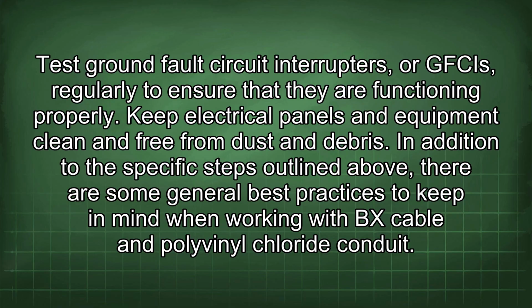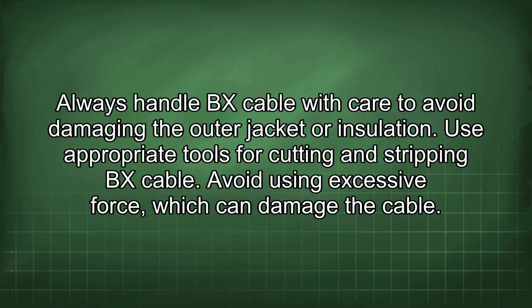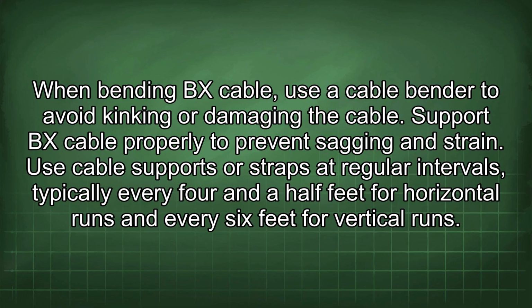In addition to the specific steps outlined above, there are some general best practices to keep in mind when working with BX cable and polyvinyl chloride conduits. Always handle BX cable with care to avoid damaging the outer jacket or insulation. Use appropriate tools for cutting and stripping BX cable. Avoid using excessive force, which can damage the cable. When bending BX cable, use a cable bender to avoid kinking or damaging the cable.